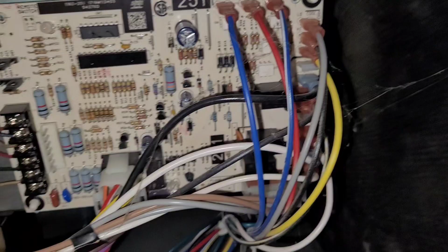We're not going to really change anything with the original thermostat wiring, except that we're going to install these two new wires. We're going to put one onto the G terminal and one onto the R terminal. So when that thermostat closes, it'll send 24 volts down to the G, which is the fan call. So the R, that just carries 24 volts, it sends it up to the thermostat. And then when the thermostat wants to bring on the heating, it sends 24 volts down on the W and on the G, depending on how the thermostat is. Sometimes it doesn't bring on the G.